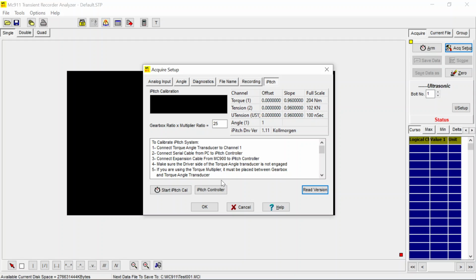At this point, we want to calibrate the iPitch with the MC950 hardware. Actually, the angle part of it. Make sure this is correct, our gear ratio and multiplier ratio. If you don't have any multiplier or standard, the gearbox is 25. If you add a multiplier to it, you have to set it to 100. So that makes the correct ratio.